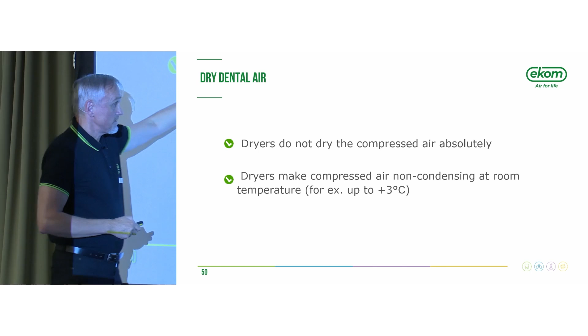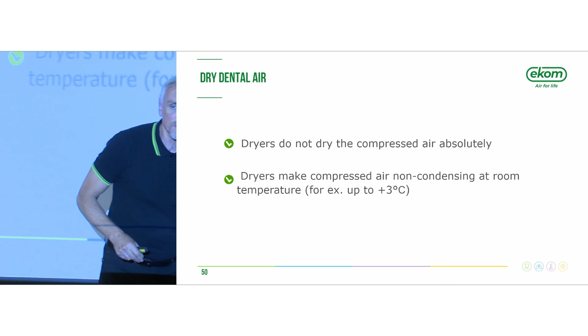But did you know that dryers do not dry compressed air absolutely? This is good to know, because somebody might think that using a dryer means absolutely dry air - this is not true, be careful. Dryers make compressed air non-condensing at room temperatures - the normal dental dryer makes air non-condensing at temperatures up to +3 degrees Celsius. If you dry the air in the hose to temperatures below 3, you'll get condensation again. But this is perfectly enough for dental use - it's a common rule accepted by dental equipment manufacturers and manufacturers of oil-free compressed air. +3 is okay.